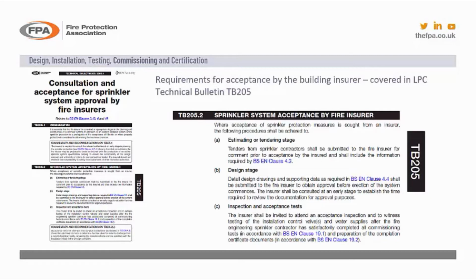Now, with regards to insurers and authorities having jurisdiction, again, if it's an LPC system, you must have an insurer involved. And with regards to the insurance, there is a specific technical bulletin that's shown on the screen, which means that you must have insurer involvement early doors. The insurers need to be involved at estimating and tendering stage. It's going to be a building that's going to be insured. And if it doesn't comply, they need to be made aware of it. If there are some deviations from standard, they need to be aware of it. If there are areas that are non-protected, they need to be aware of it. And this is all done at estimating and tender stage.